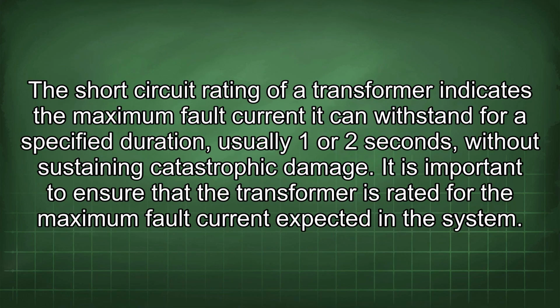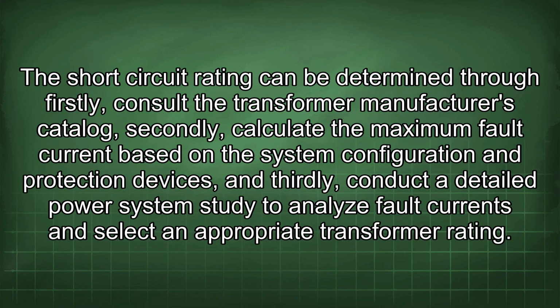The short circuit rating of a transformer indicates the maximum fault current it can withstand for a specified duration, usually 1 or 2 seconds, without sustaining catastrophic damage. It is important to ensure that the transformer is rated for the maximum fault current expected in the system. The short circuit rating can be determined through, firstly, consulting the transformer manufacturer's catalog; secondly, calculating the maximum fault current based on the system configuration and protection devices; and thirdly, conducting a detailed power system study to analyze fault currents and select an appropriate transformer rating.